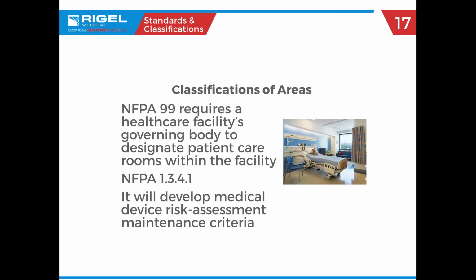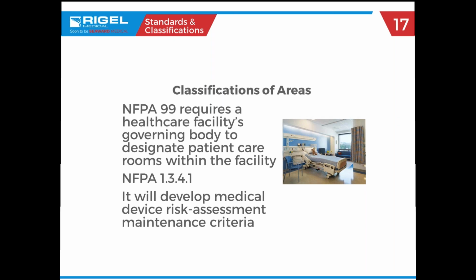So a few years back, they started looking at classifications of areas within a facility. They were basically trying to identify the risk associated with an area. NFPA 99 requires healthcare facilities to designate patient care rooms throughout their facility, very creatively named Category 1, Category 2, Category 3, and Category 4. But we're going to look at those a little bit more closely now.